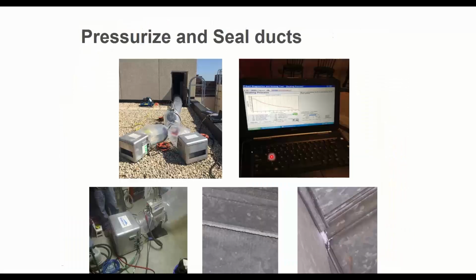So the technician is watching this on their computer as it happens. They're seeing the leakage rate in real time. It's constantly calculating every minute. And they're seeing it drop down and down and down. And they keep going until they either get to the leakage rate that is required by whatever specification they're trying to meet, or until things kind of flatline. And it's like, okay, we've gotten down to the practical point here. I can't chase the last 8, 12, 50 CFM. I'm kind of at a practical conclusion.